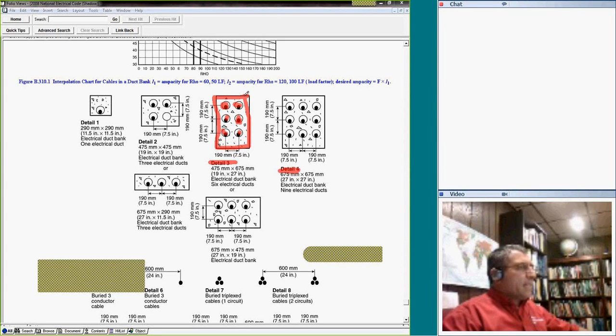I'm going to be using this one in particular, just to give you an idea. I have 6 circuits in parallel in underground ducts encased in concrete, commonly used electrical ducts. Each one of them has phase A, phase B, phase C in it. You can see that. That's the version we're going to be using. Also, you can put one duct at a time, or 2 ducts. You can have direct burial, and all these configurations. I'm going to highlight this particular one. Just remember how it's going to look when you see detail number 3.